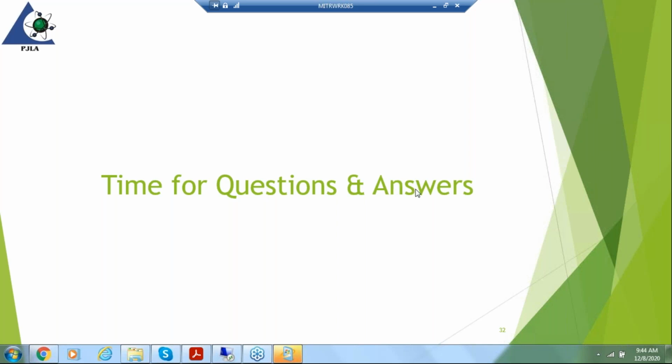Okay, just some feedback on the one question we had about PT, proficiency testing for microscopic methods, is that there's difficulty finding another laboratory to compare results with that's local. So every accreditation body, and even our own policy, we have room for alternatives. So our proficiency testing policy requires that the laboratory either choose a third-party proficiency testing provider, compares results through interlaboratory comparisons with associations or with other laboratories with the same accredited scope or same equipment technology. But if they can't, then there has to be an alternative. So laboratories could use 2 technicians within their laboratory, which is intra-laboratory, or repeatability studies may be used.